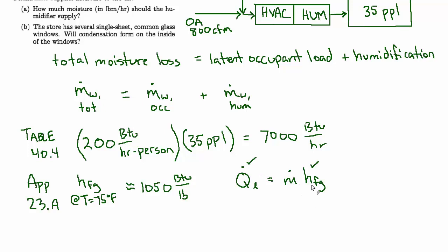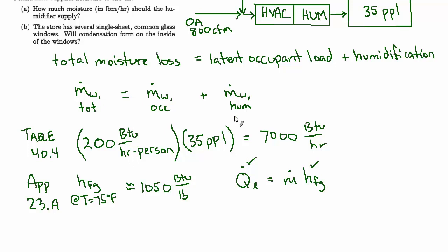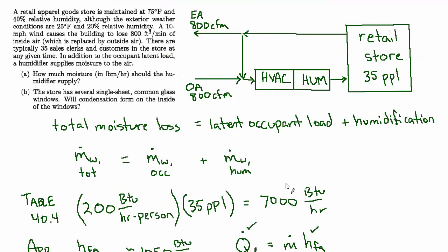And now I'm going to come back to using these subscripts for clarity. This ṁ is actually the mass flow rate of water vapor produced by occupants—the latent occupant load. ṁ_w for the occupants equals 7,000 BTU per hour divided by 1050 BTU per pound, which is 6.67 pounds per hour. So we just found this number.